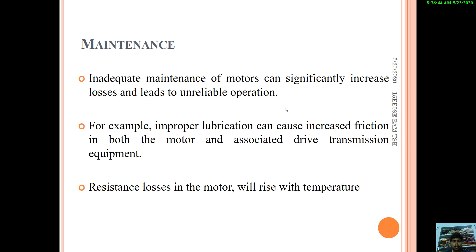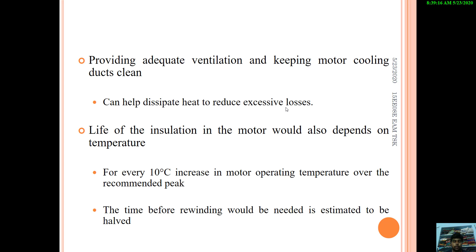This can be avoided by providing adequate ventilation and keeping motor cooling ducts clean, which will help to dissipate heat and reduce excessive losses. The life of the insulation in the motor also depends on temperature. For every 10 degree Celsius increase in motor operating temperature over the recommended peak, the time before rewinding would be needed is estimated to be halved.